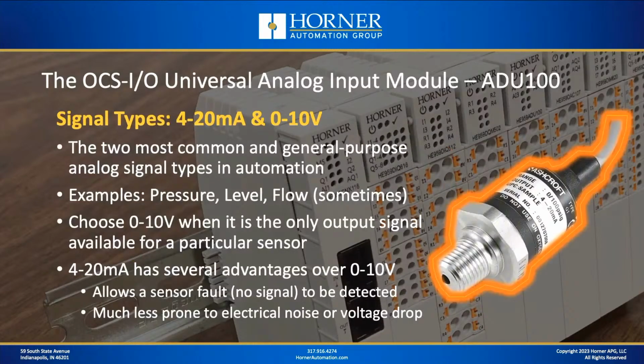Let's start with the signal types of 4 to 20 milliamps and 0 to 10 volts. These are the most general purpose and the most common in automation. Examples would be pressure sensors, level sensors, sometimes even flow sensors, and there's literally thousands of sensors available that support these ranges. Now, when would you choose 0 to 10 volts over 4 to 20 milliamps and vice versa? Generally, you should only choose 0 to 10 volts when it's the only output signal that's available for a particular sensor. Why would you choose 4 to 20 milliamps instead?